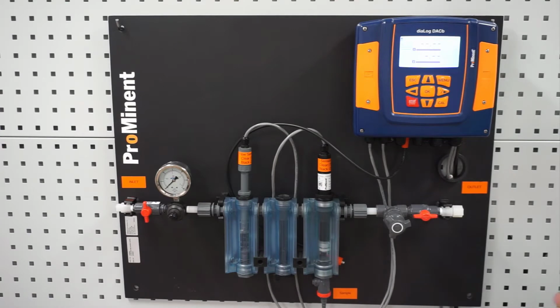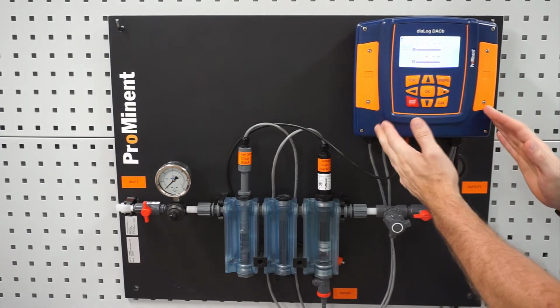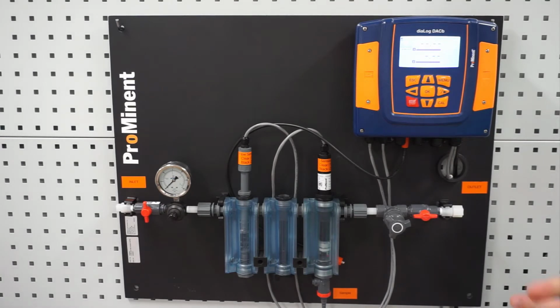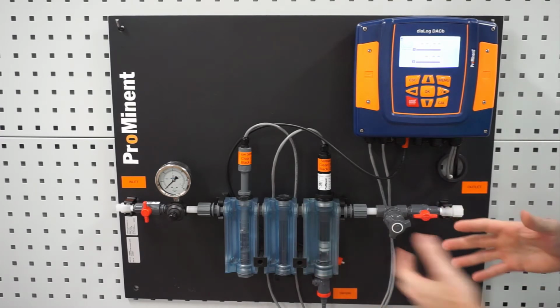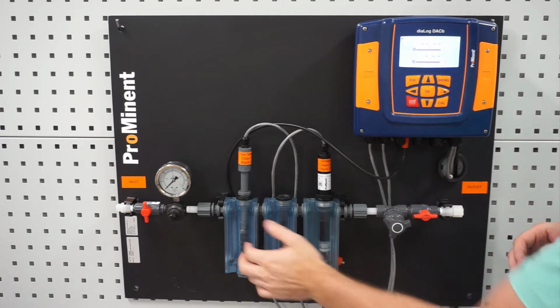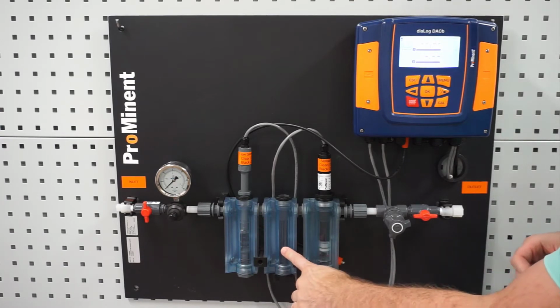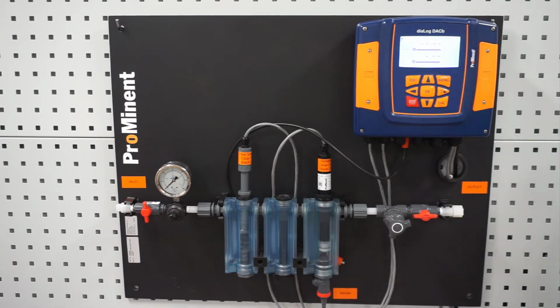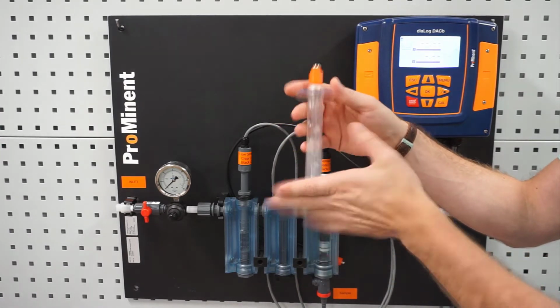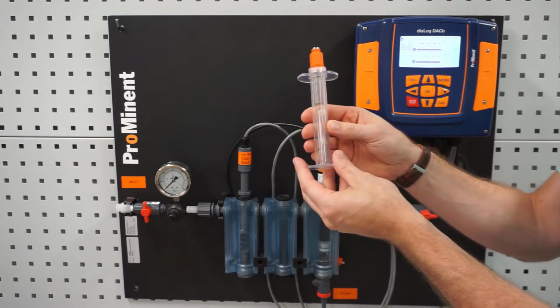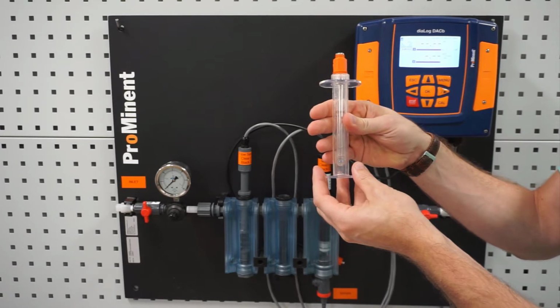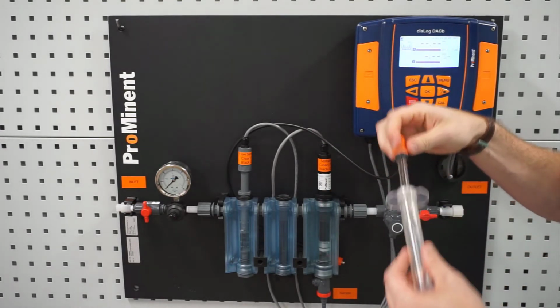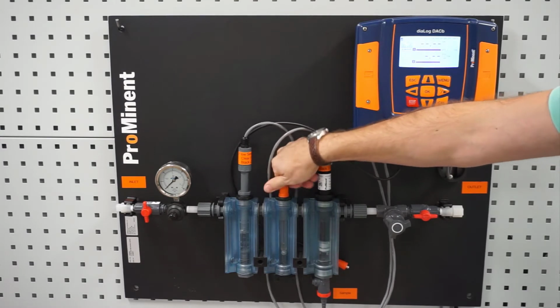A flow sensor is very important if we are controlling directly from our DACb. It will tell us if we lose flow. It will recognize that in the controller and that will shut down all of our pumps that we're controlling directly from here. That way we are not pumping chemical into a stagnant line. So that is for safety. Next we have a place to put our pH sensor. Your pH sensor will ship loose. It is shipped in a holder, and in that holder there's going to be a liquid that keeps the sensor alive. So we will take that sensor off and thread it into our DGMA flow cell.